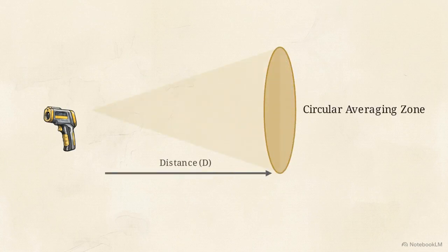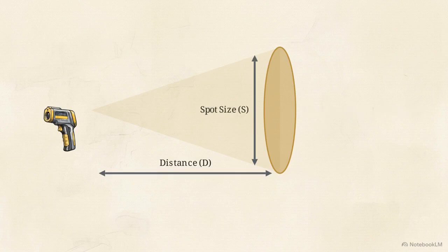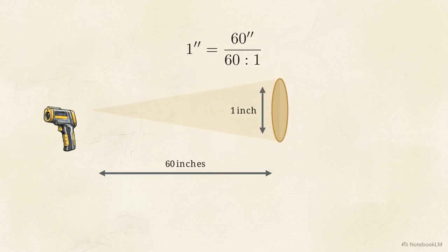A non-contact infrared sensor does not measure a single microscopic point. It measures the average temperature across a circular surface area. This diagram demonstrates the distance-to-spot ratio. Spot size equals distance divided by the instrument's D to S rating. The MX6's 60:1 ratio measures a 1-inch target from 60 inches away. If the component is smaller than this spot size, the sensor absorbs background radiation, corrupting the data.